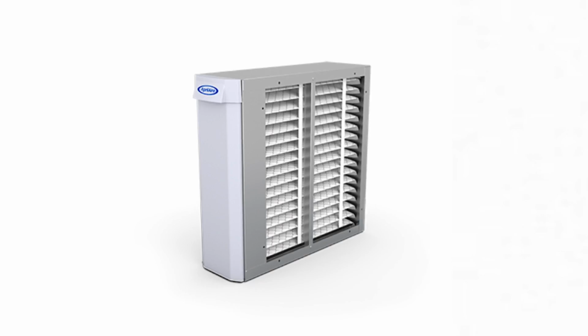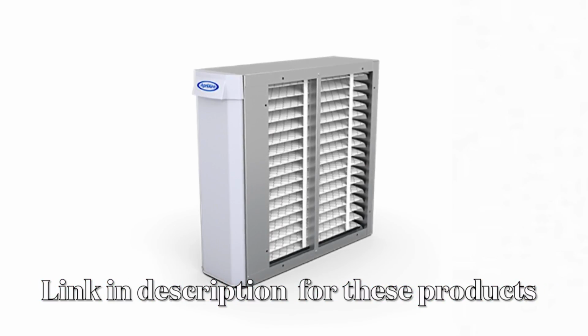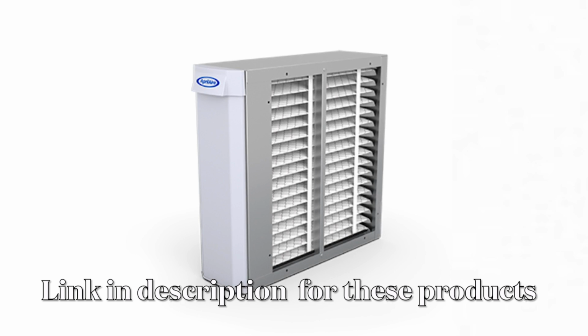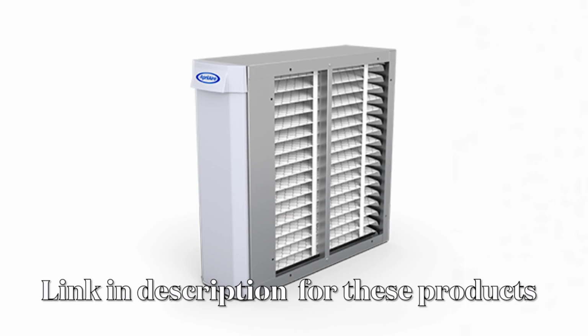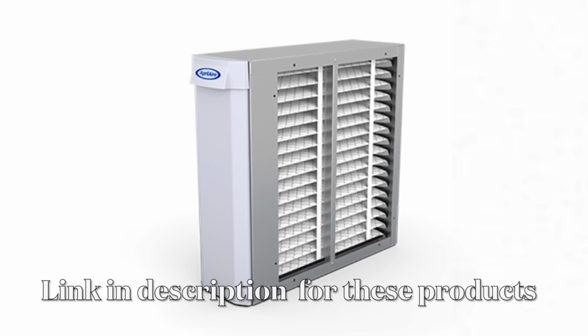Instead, maybe look at some of these whole house filter options. There's several out there. They're usually a little thicker in size. Instead of being only 1 inch, the filter is going to be more like a 4, 5, or 6 inch filter. A lot of them have pleats, so if you were to cut the ends off and stretch the filter out, you'd have much more surface area. That's how they keep static pressures down.